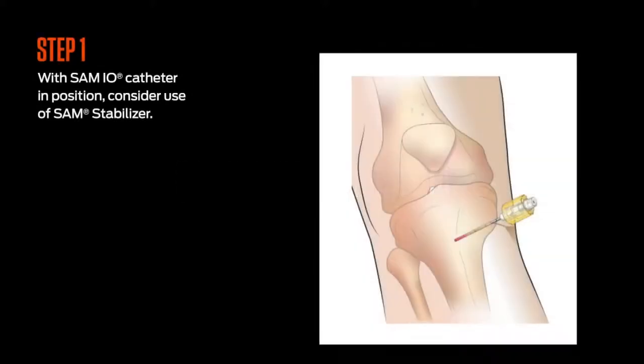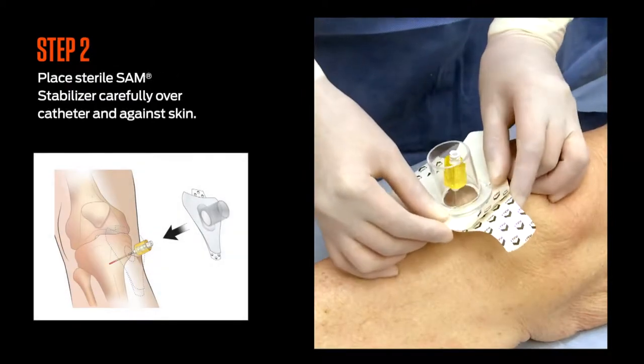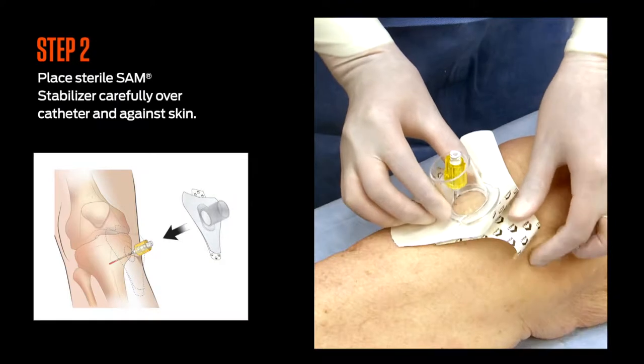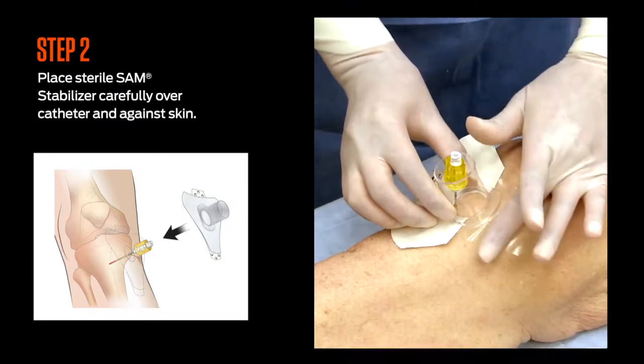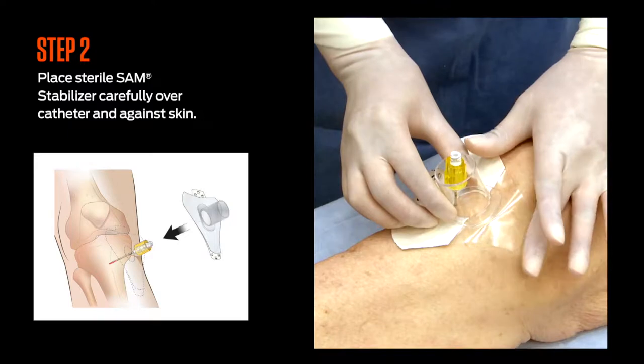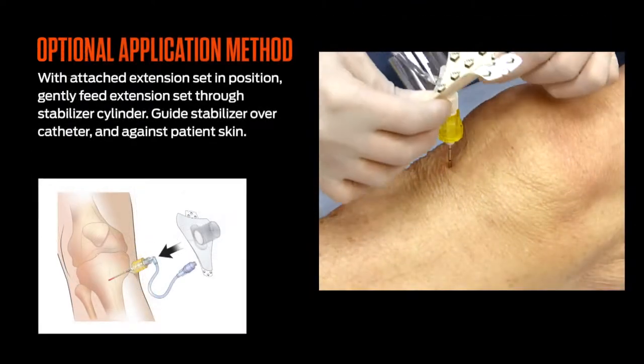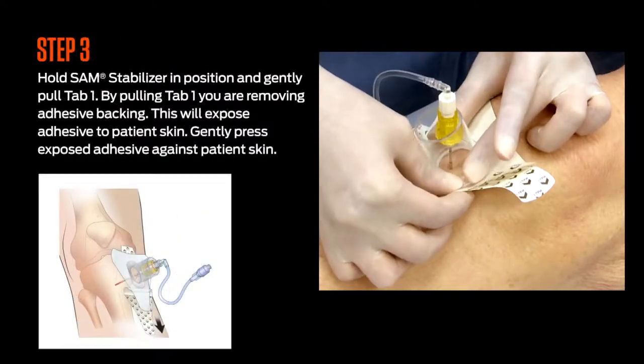The following is supplemental material. With the I.O. catheter in position, consider using the SAM stabilizer. There are two methods to attach the SAM stabilizer: place it carefully over the catheter and against the skin, then attach the primed extension set to the SAM.IO catheter; or alternatively, attach the extension set first and then apply the SAM stabilizer.